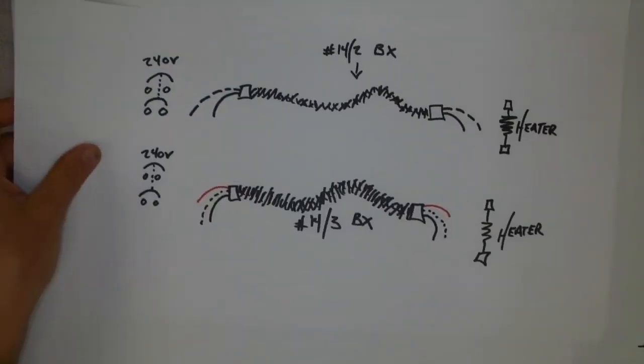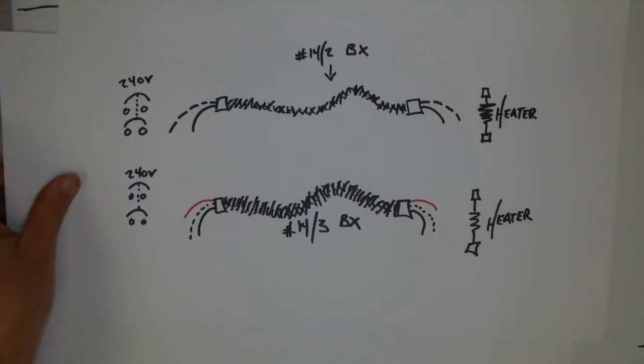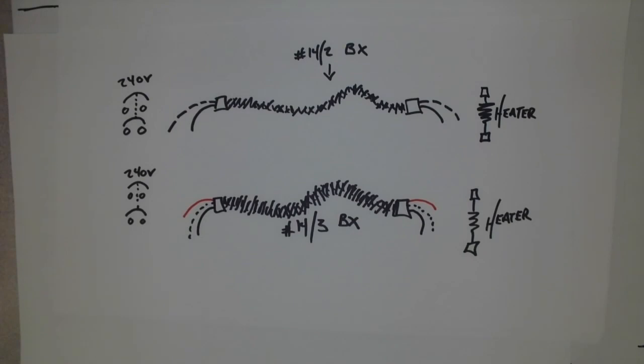We said sometimes you're going to run into situations where you have a cable, but the cable doesn't match the coloring that's required by the CEC. So remember, the coloring of conductors is listed in section 4032. So rule 4032 is identification of insulated conductors. If my conductor coloring doesn't match what's given in 4032, then I need to either pull in new conductors or take a look at 4030.